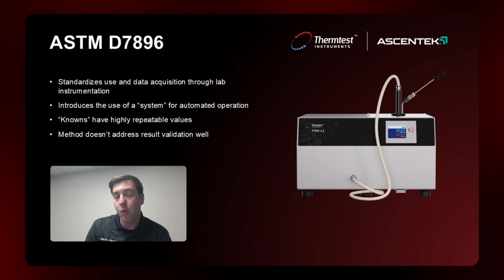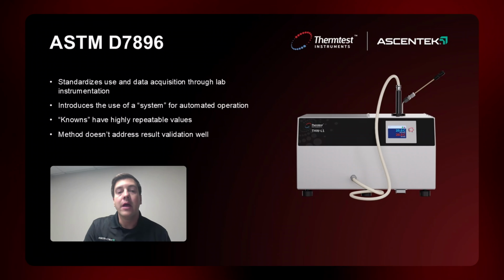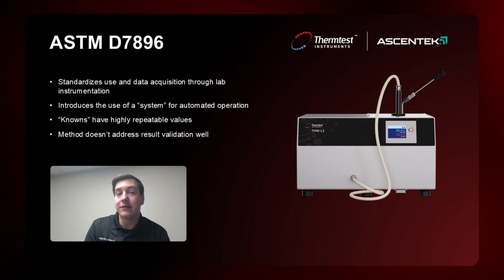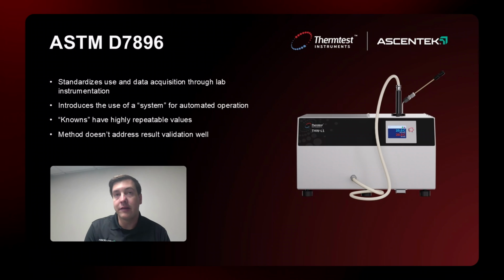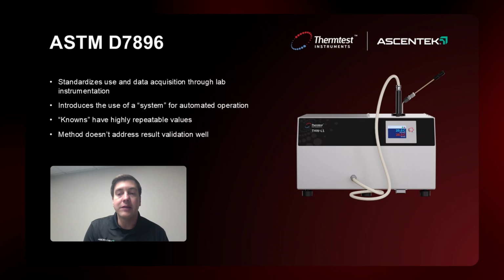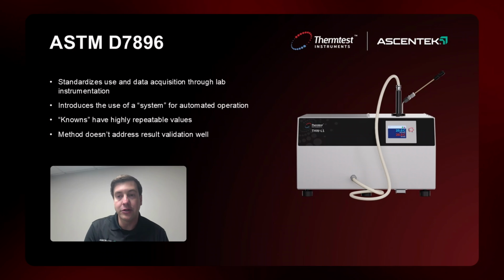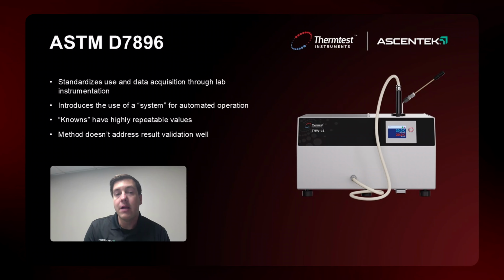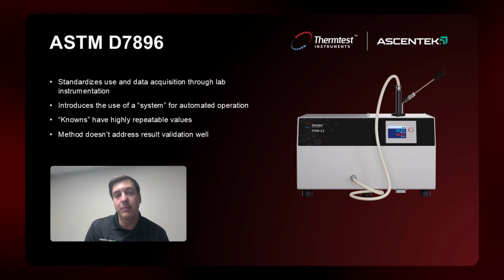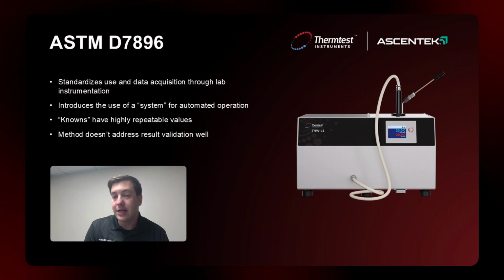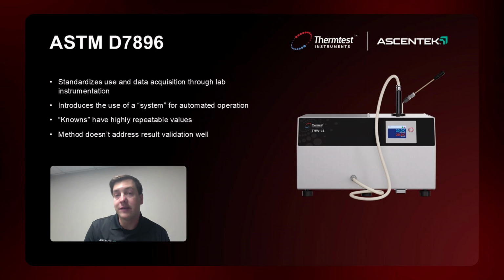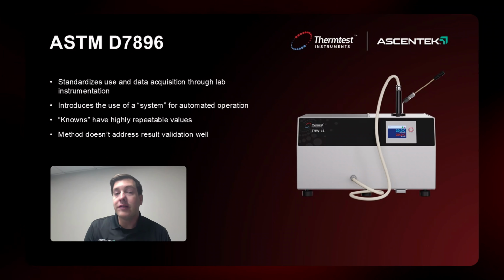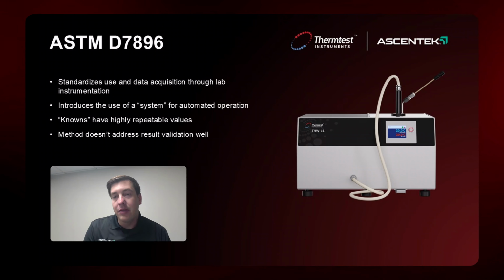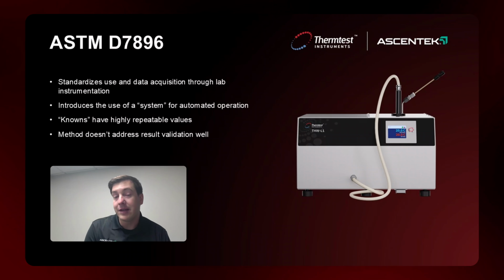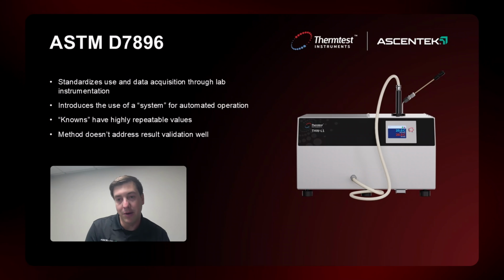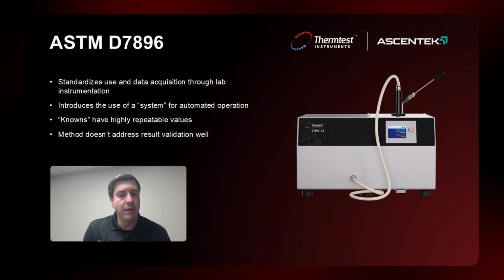It's been around for quite some time, at least from a theory and a practicality standpoint. But it really wasn't until the use of ASTM D7896, the method held within Subcommittee D15 on antifreeze and heat transfer fluids, that this was taken to a preset way to measure accurately, repeatably, and in an automated fashion. This method introduces what they call a system, or basically the ability to build in automation or instrumentation to make this analysis and data acquisition all happen in one nice little package. Within D7896, you get that standardization, and actually the image used within that method of what a standard setup looks like is an actual Thermtest instrument as well. So it's been paved by Thermtest from the start.